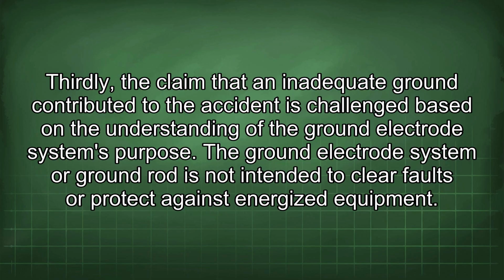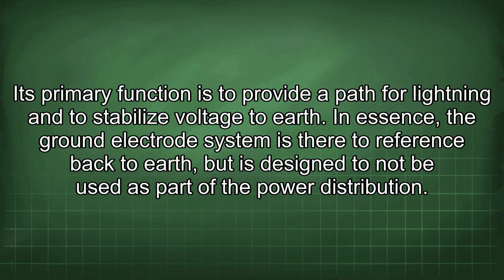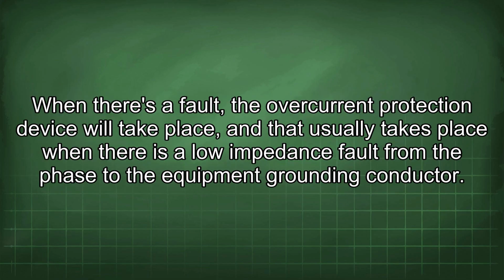Thirdly, the claim that an inadequate ground contributed to the accident is challenged based on the understanding of the ground electrode system's purpose. The ground electrode system or ground rod is not intended to clear faults or protect against energized equipment. Its primary function is to provide a path for lightning and to stabilize voltage to earth. In essence, the ground electrode system is there to reference back to earth, but is designed to not be used as part of the power distribution. When there is a fault, the overcurrent protection device will operate, and that usually happens when there is a low impedance fault from the phase to the equipment grounding conductor.